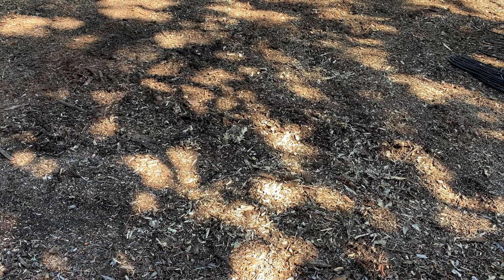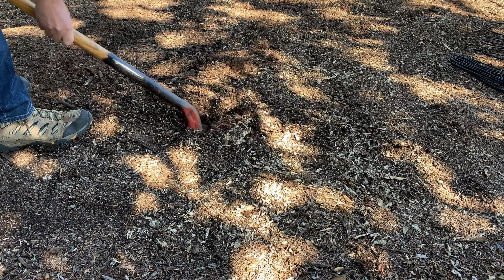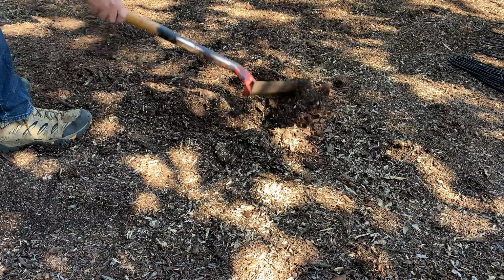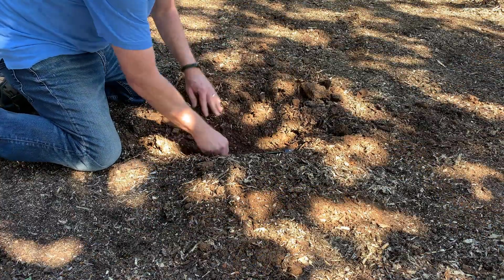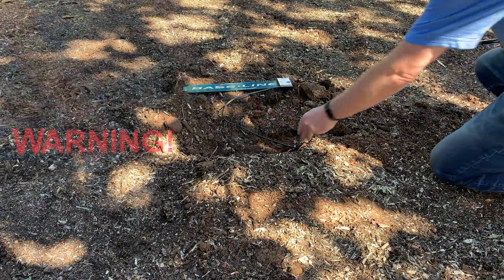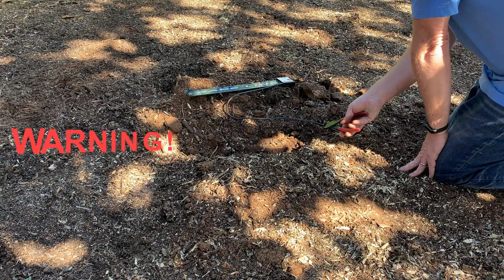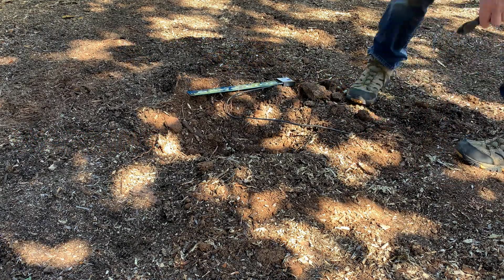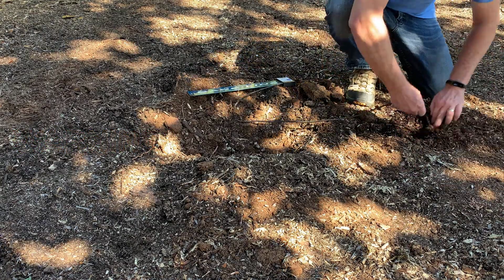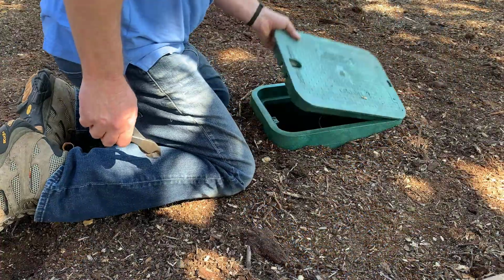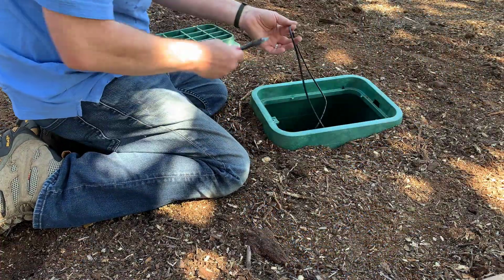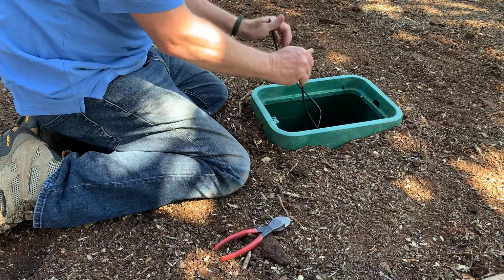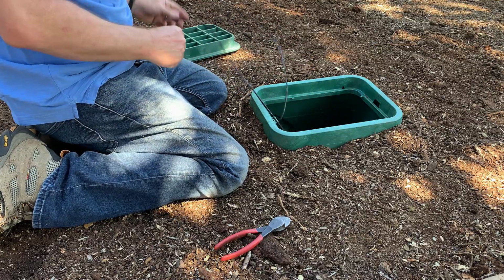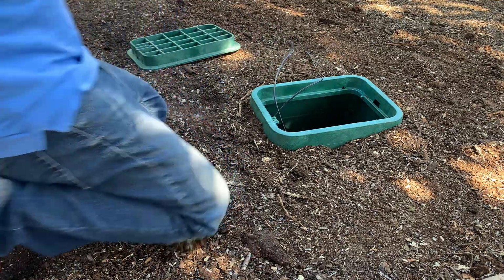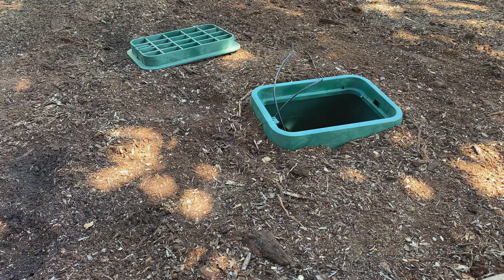We've taken the initial steps at the controller, so it's time to go out to the field where the soil moisture sensor is installed and carefully dig it up. Be careful not to damage it though. We need to remove the sensor, but it's a bad idea to cut the wire this short. Consider removing the wire all the way back to the box where the original splice was made, saving the entire wire length. Remember that industry standards call for splices to be made in a pull box with 18 inches of slack. Taking the time now will make reinstalling the device easier later on.